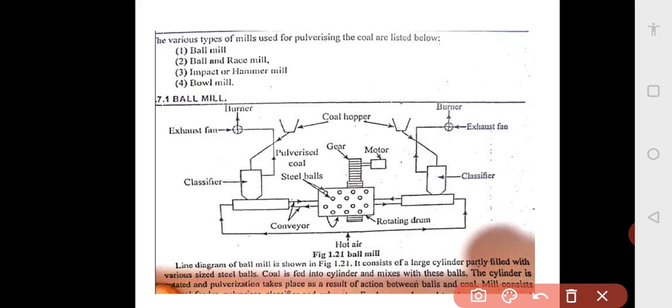This is the ball mill. It uses steel balls in the drum. Coal is fed into the drum, and the drum is rotated with a motor and reduction gearbox. Conveying of the pulverized coal is done by hot air, separated in the classifier, and flow is controlled by dampers in the exhaust fan.